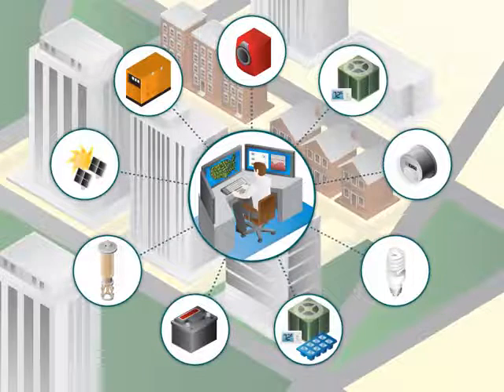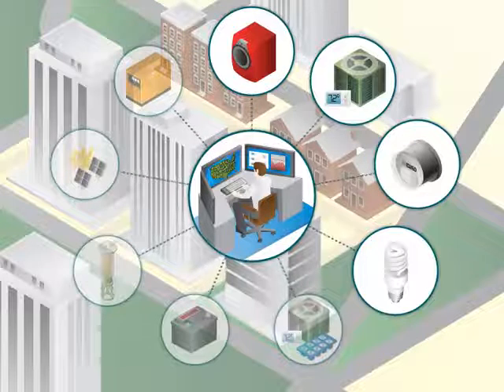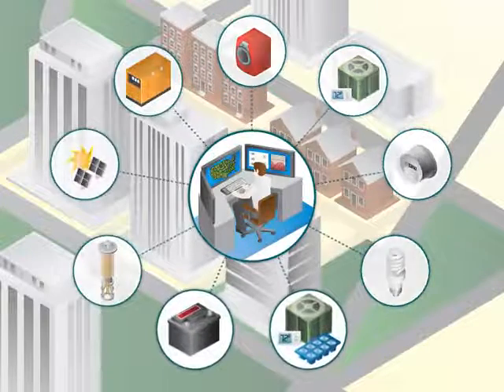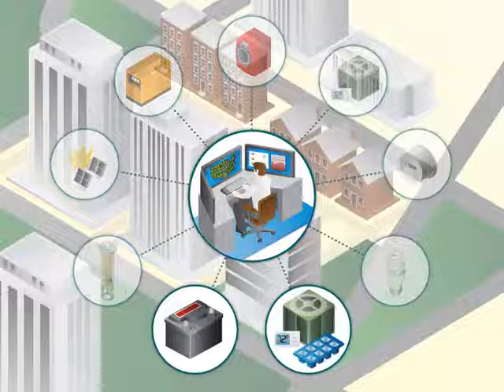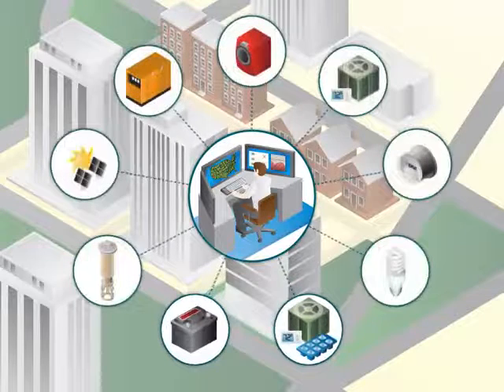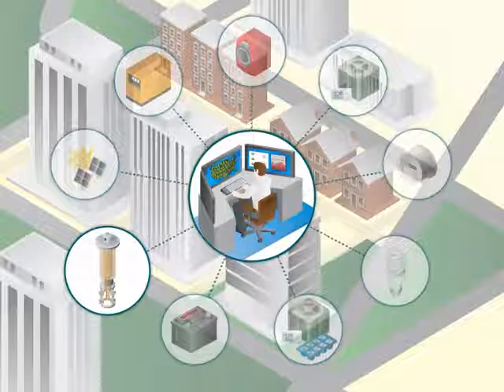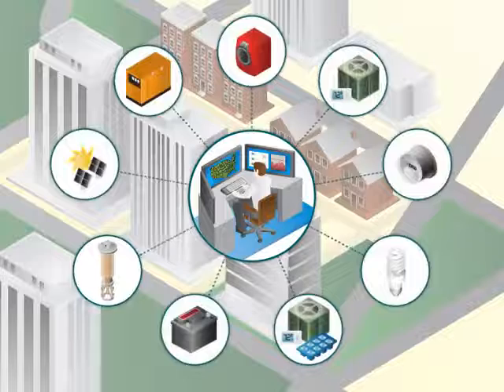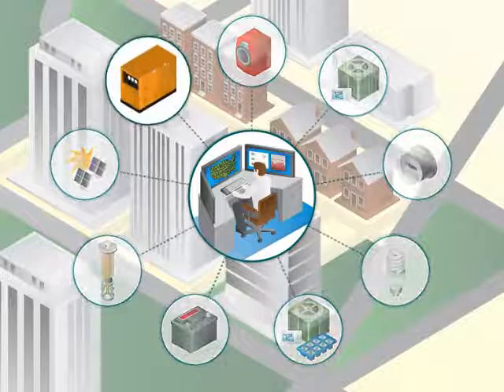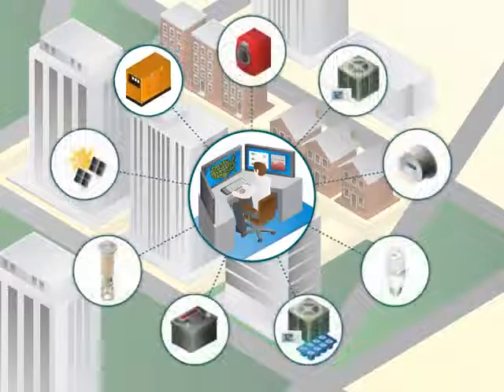Examples of these resources are smart meters and smart appliances that are distributed throughout the grid and enable demand response, which encourages the shedding of load or turning off of appliances during constrained conditions. Energy and thermal storage technologies throughout the grid store electrical or thermal energy during off-peak times and discharge during peak times. Conservation voltage reduction is a process to systematically reduce voltages on the distribution network, resulting in a proportional reduction of load. Solar technology is also deployed to provide renewable energy generation. Conventional distributed generation is used as emergency backup for customers and can also be leveraged as a resource.